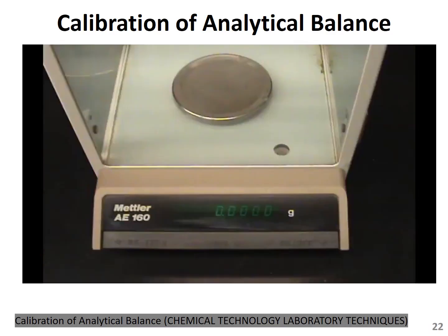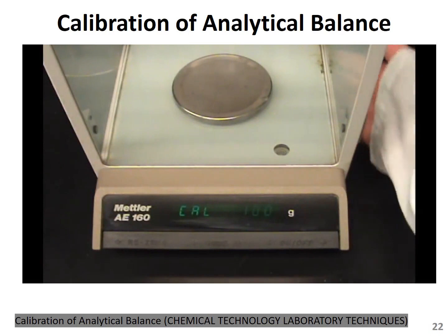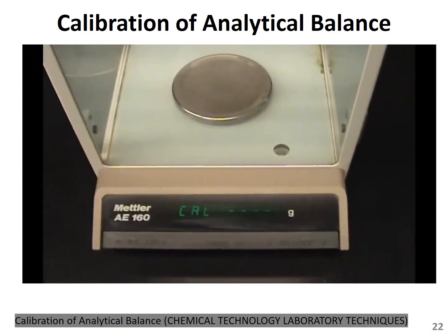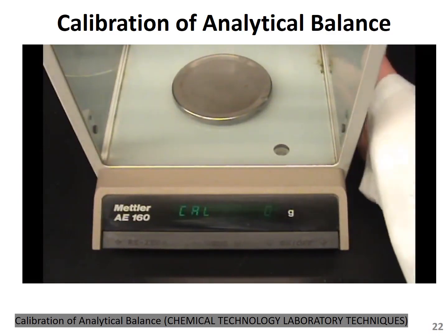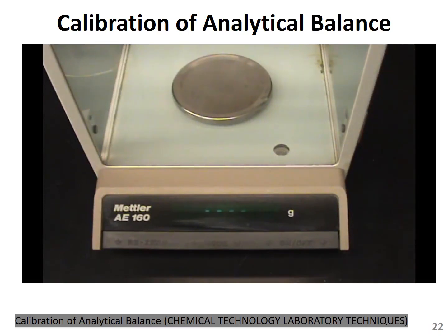Turn on the balance. A warm-up time of 30 minutes is suggested for optimal performance. When 0 appears, press and hold down the control bar where it says Mode. When Cal with dashed lines appears on the display, release the bar. Cal 100 will flash after a few seconds. Slowly move the calibration lever on the lower side of the balance toward the rear. Cal with the dashed lines will appear, and then 100. When the display Cal 0 appears, move the lever back to the original position. Dashes will flash, followed by 0.